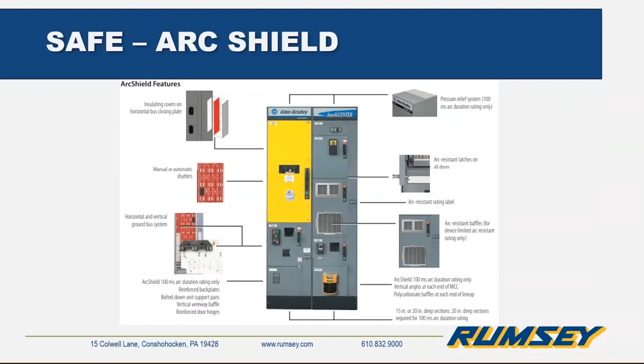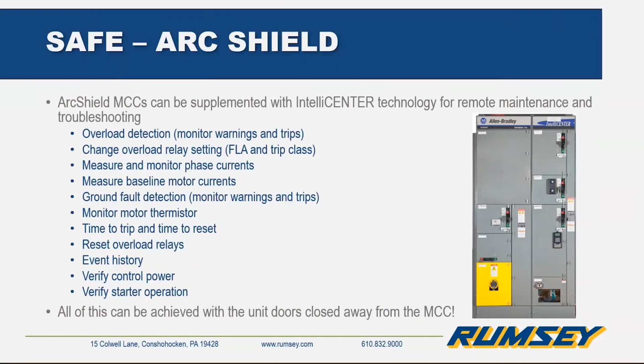So we are going to talk about IntelliCENTER in depth later on, but I wanted to show you this now because IntelliCENTER and ArcShield can actually be used together for an even greater level of safety. And what we're talking about here is basically remote troubleshooting and maintenance, which allow all of the tasks that you see on this list to be completed without even going near the MCC and with all the unit doors remaining closed. So this obviously limits the exposure of personnel to dangerous voltages and hazards. As you can see from this list, you can do quite a lot without even going in or near the MCC. And more on that later.